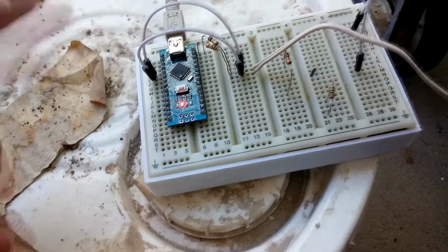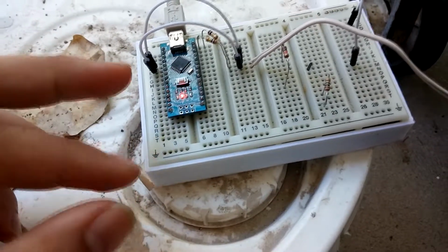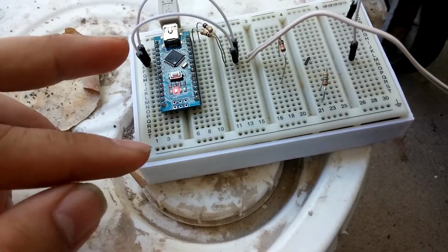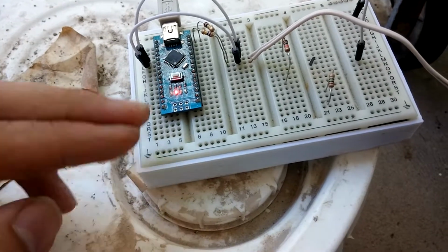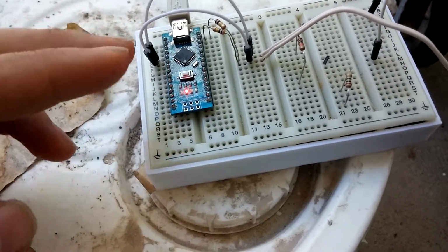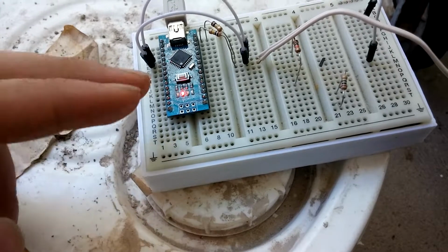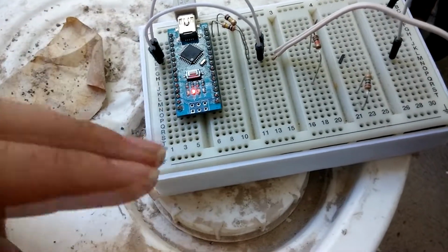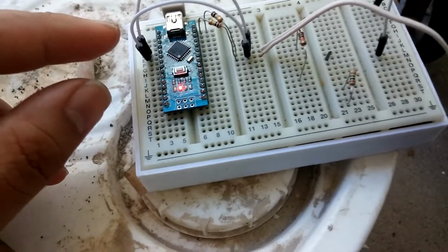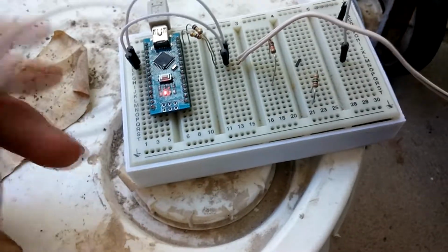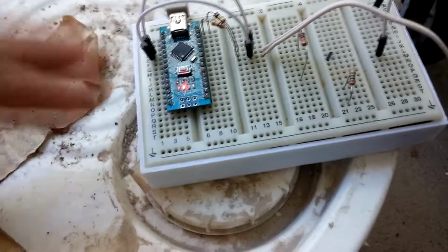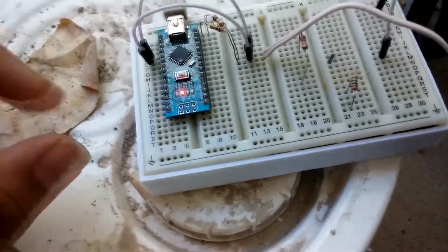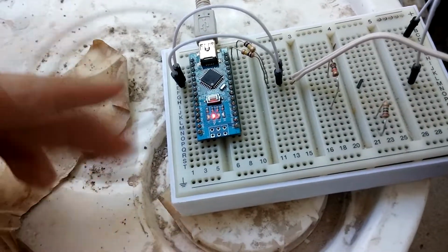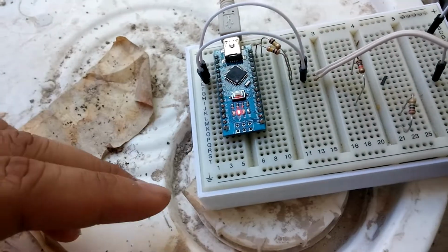If you've done any chemistry or know how electrolysis works, you'll know the copper likes to migrate depending on the current flow. So if we put it one way, copper goes from this terminal to that one, and if we swap them around, it goes the other way. So it's constantly switching every time we do a reading—not really fast, just switching between readings.